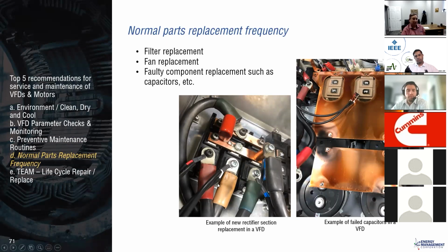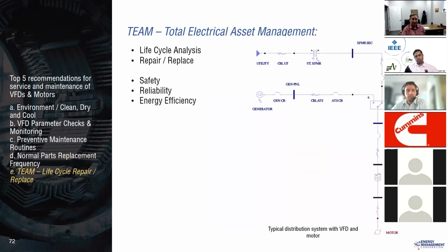Here's a diode failure, a typical diode failure. And we're finding that keeping that DC bus operating correctly is an important piece of it. So with this total electrical asset management concept, we'll go into a facility and analyze: is the equipment current generation? Is it a legacy product? Is it obsolete? Are spare parts available? And we'll do an analysis with that customer with a view to, okay, does it make sense to replace the drive?